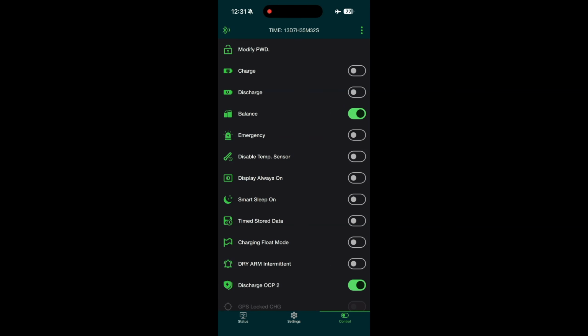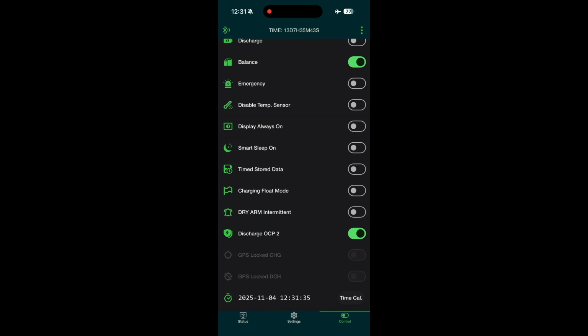Dry alarm, or dry arm intermittent - this is basically an external programmable function for the BMS to control external devices like a relay, based on different states of charge or similar. Discharge OCP, which is Over Current Protect 2, is basically the second layer of over current protection when discharging.